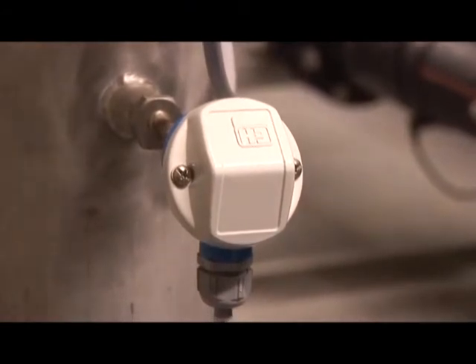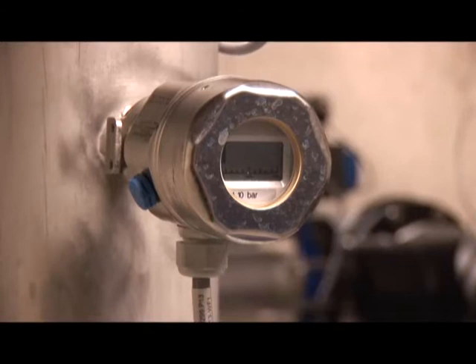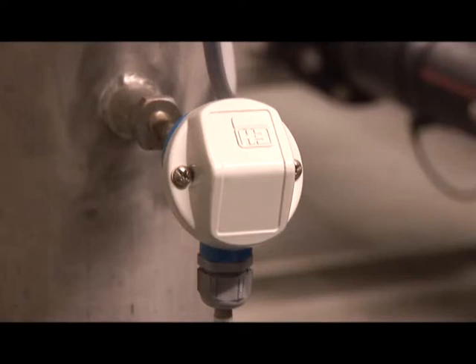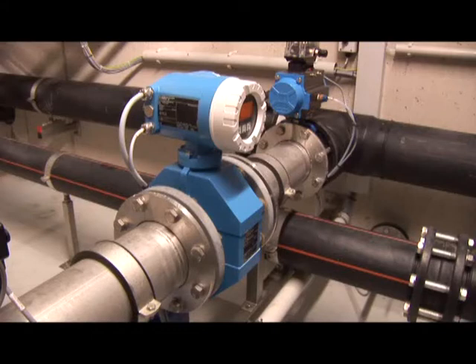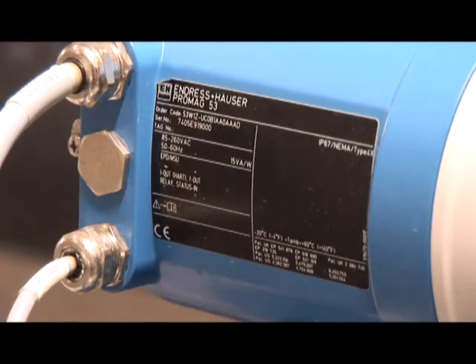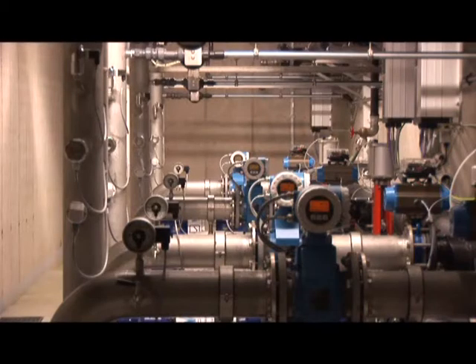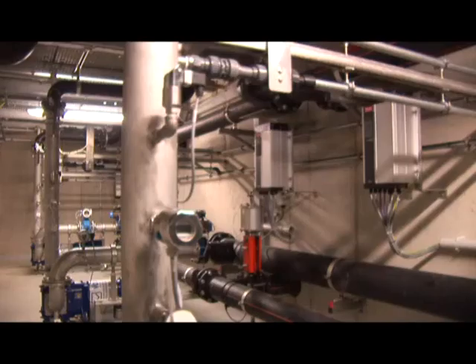to prevent overpressure. In addition, for each chamber, a Cerabar M PMC is installed for vacuum monitoring, and a temperature safety switch is installed which shuts off if temperatures are over 40 degrees Celsius. The flow is measured with the Promag W. This overpressure measurement is necessary so that the pump is not damaged during reverse rinsing, which takes place every 10 minutes.